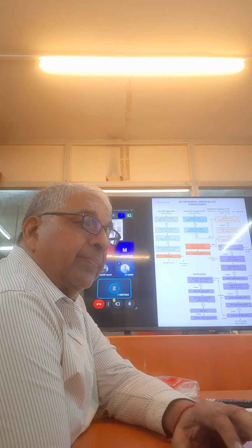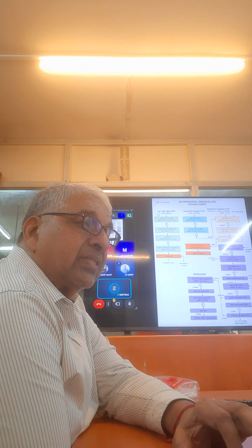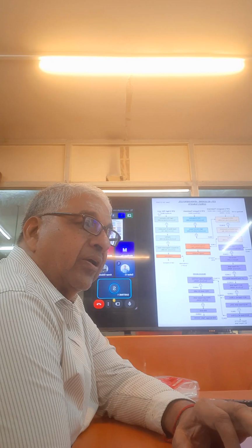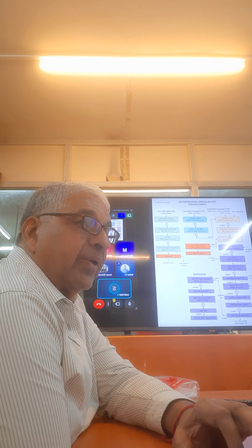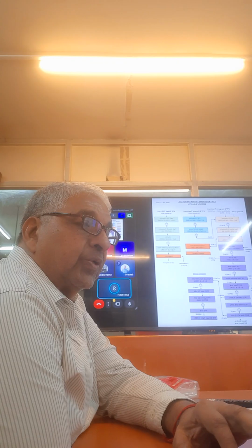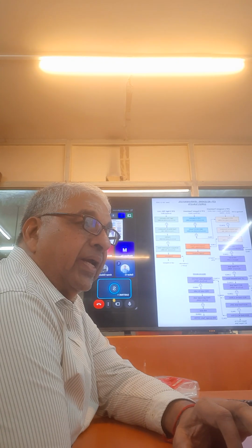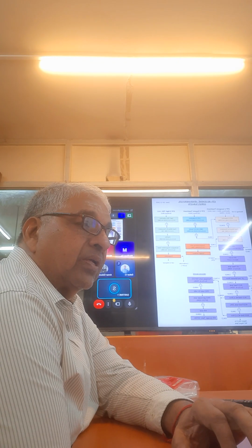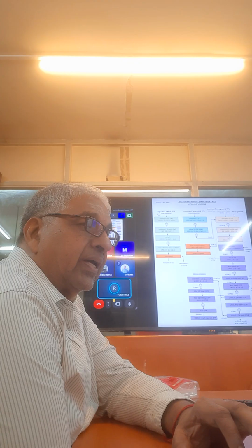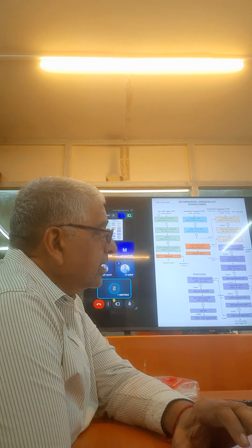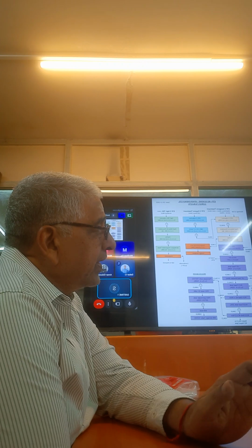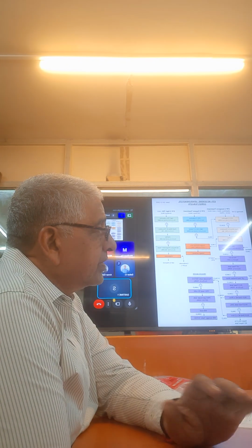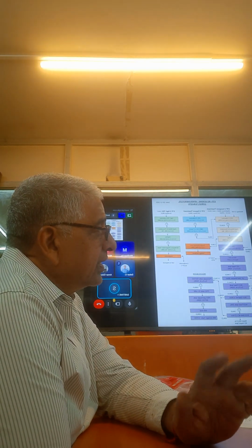Now the dump, I have revised it. It is 3 KLD based on the data you gave me yesterday. So it will be 3 KLD and the reject will be 8. So the high TDS water, 3 KLD itself is on the higher side. I get only 1.8. If you add weekly everything and divide it by 7, monthly everything divided by 7, it's not a big volume.